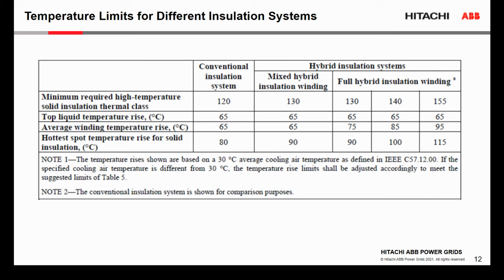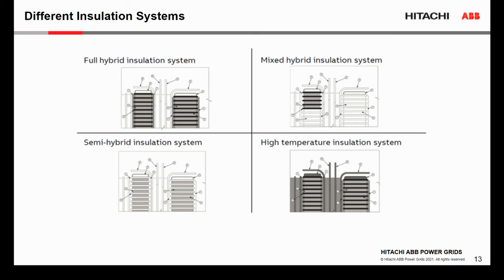We can increase the temperature limit by using a different type of paper covering or different material for the insulation. So if we change the paper on the conductor to a high temperature material, we can increase the hot spot rise to 90 degrees, or in some cases even to 115 degrees. At the same time, the absolute temperature limit will change from 120 to 130 or even 155 degrees C.